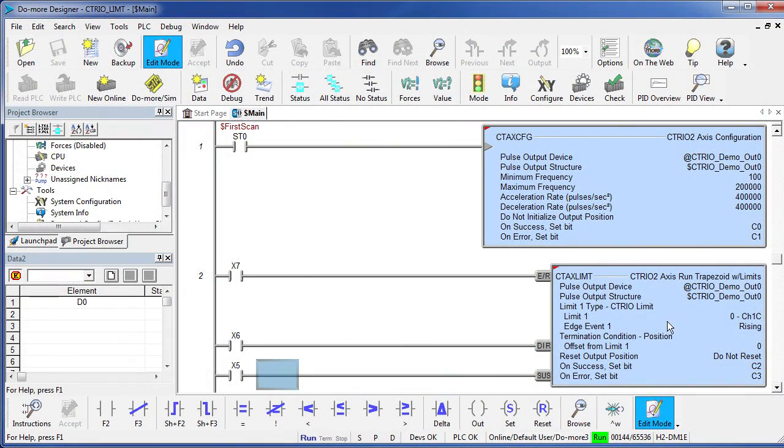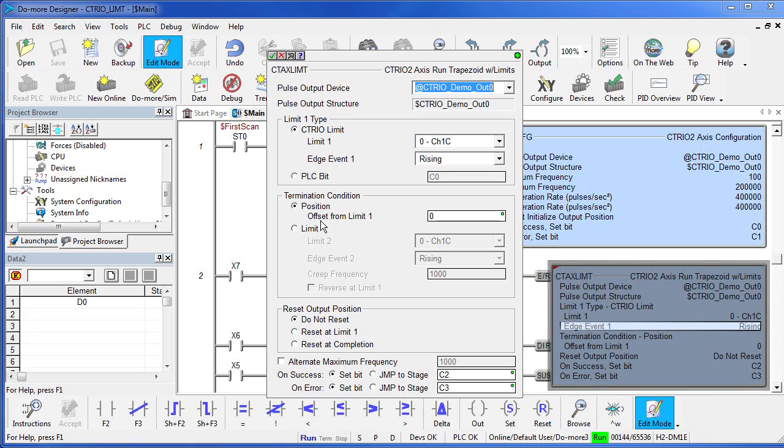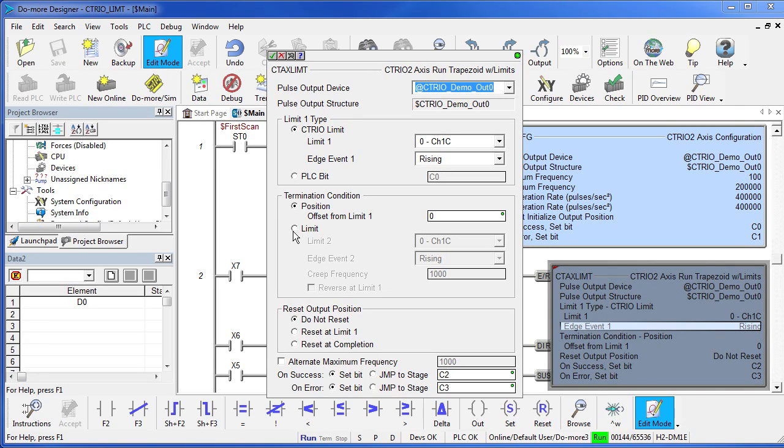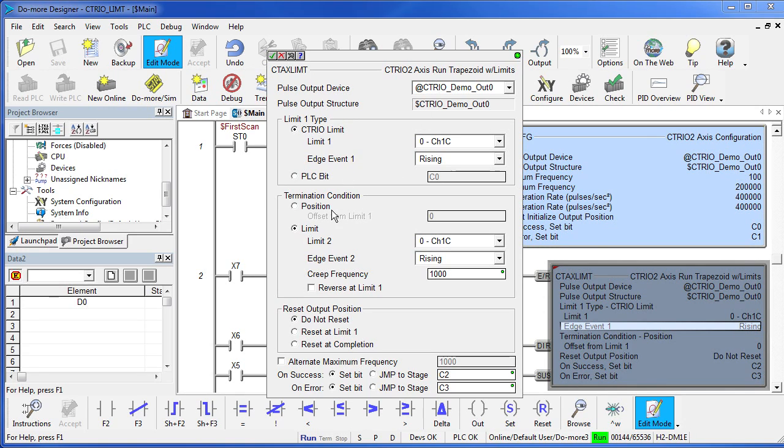If you go back into this dialog, notice that instead of going back to the original position, we could actually tell it to go to a second limit switch if we wanted to. It would hit the first limit switch, ramp down, and then creep at whatever frequency you specify here until it finds the second limit switch.